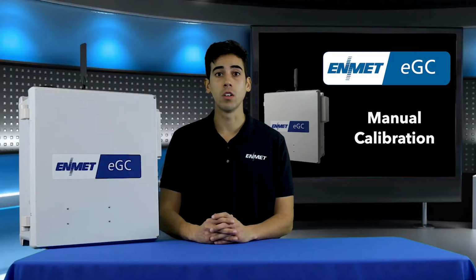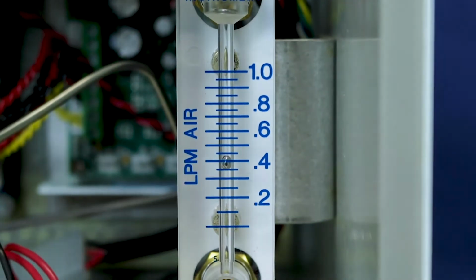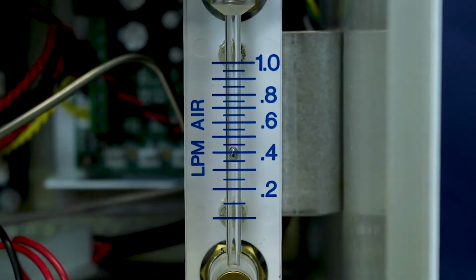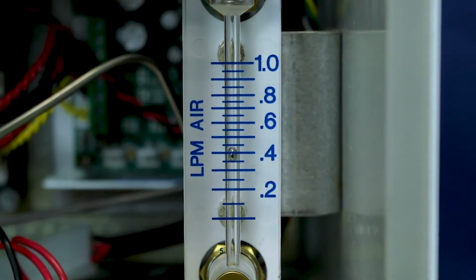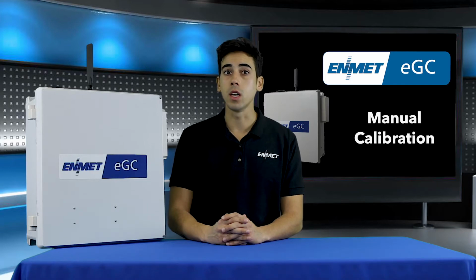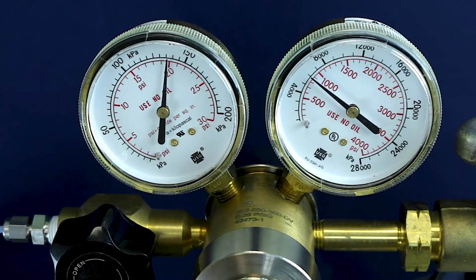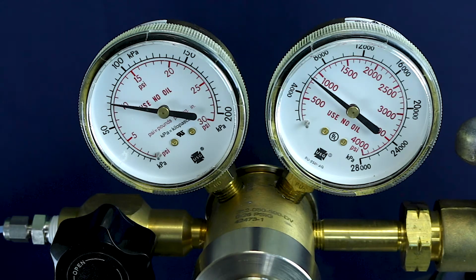The second stage pressure can be adjusted up or down by a few psi if necessary to maintain a flow of about 0.5 lpm as observed on the flow meter within the enclosure during the 45-second sampling period of the calibration run. Typically, the value ranges from 5 to 8 psi. It is extremely important that you maintain the second stage pressure below 20 psi, or the calibration gas solenoid valve will leak and the calibration gas cylinder will be drained prematurely.